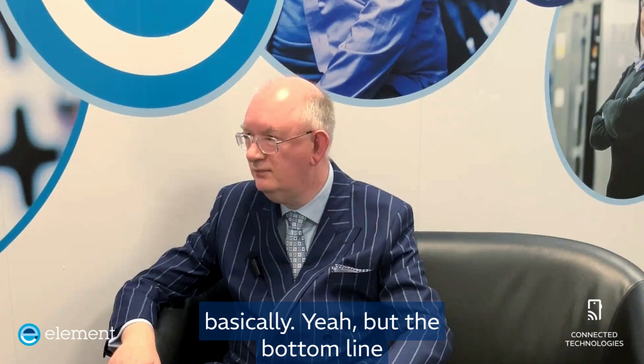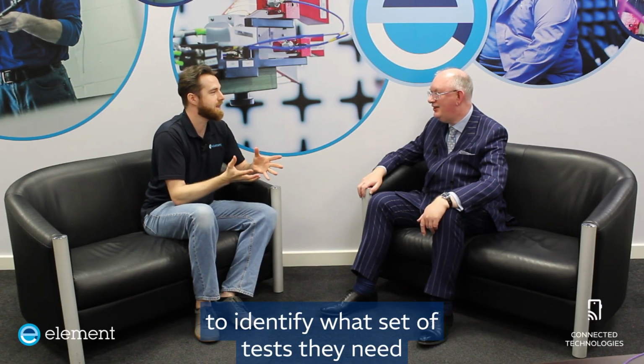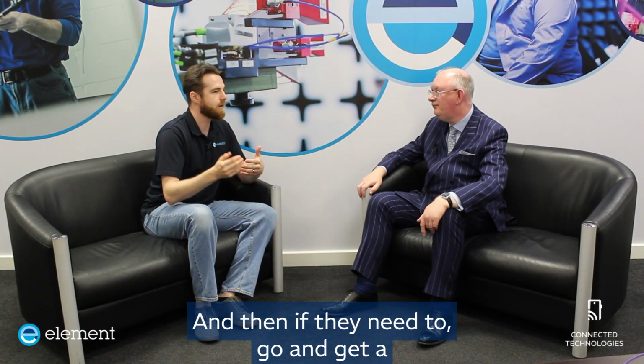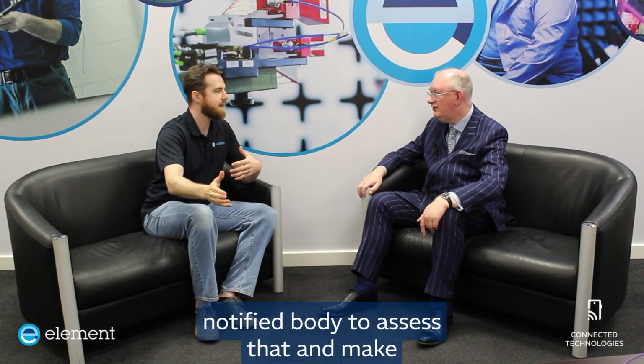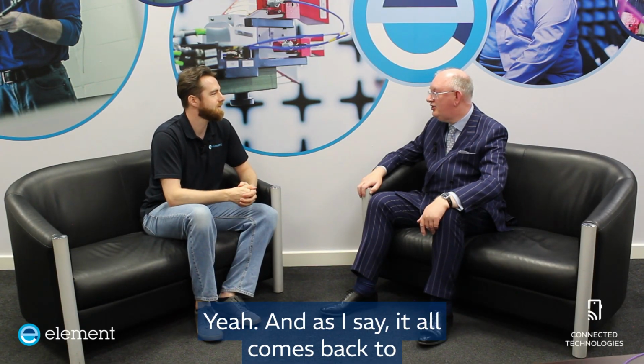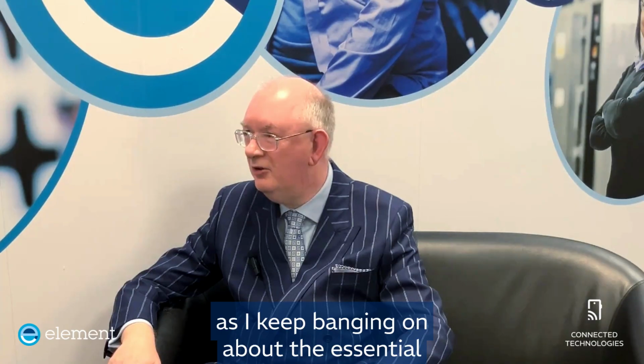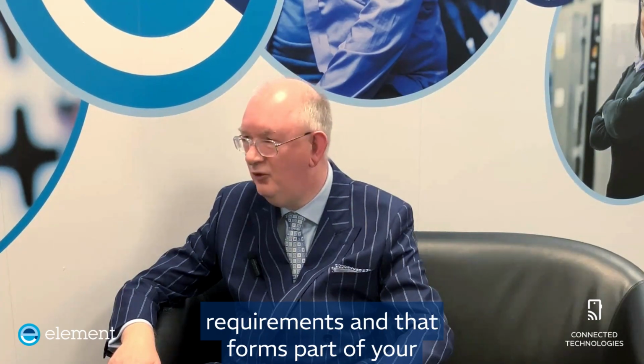Yeah, but the bottom line really is the manufacturer, and this really underscores everything we've been saying for the last 15 minutes. So the manufacturer should do a risk assessment to identify what set of tests they need to do, whether that's drawing from harmonised standards, other specifications, what performance criteria they use, what environmental profiles. And then if they need to, go and get a notified body to assess that and make sure it's right. And if they need guidance on coming up with that risk assessment, well, there are outfits out there like ours who can help with that. Yeah, and as I say, it all comes back to, as I keep banging on about, its essential requirements, and that forms part of your essential requirements.